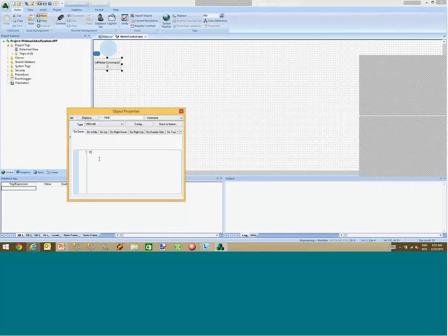In VB script, before using the custom property, you use the dollar sign to indicate it's going to be an InduSoft component, and then the custom property, colon, and if you want a default value, the default value. So I can say if motor command is equal to zero, then $motor command equals one, else motor command equals zero.